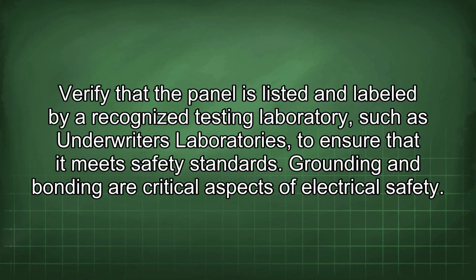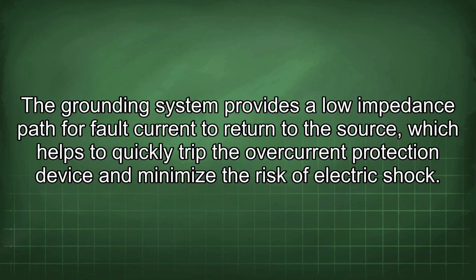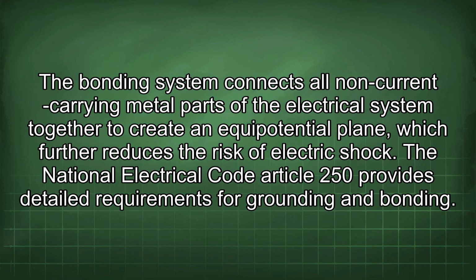Grounding and bonding are critical aspects of electrical safety. The grounding system provides a low impedance path for fault current to return to the source, which helps to quickly trip the overcurrent protection device and minimize the risk of electric shock. The bonding system connects all non-current carrying metal parts of the electrical system together to create an equipotential plane, which further reduces the risk of electric shock. The National Electrical Code Article 250 provides detailed requirements for grounding and bonding.